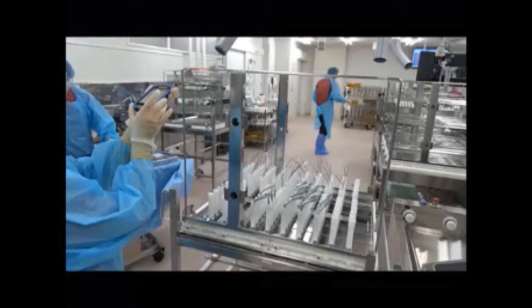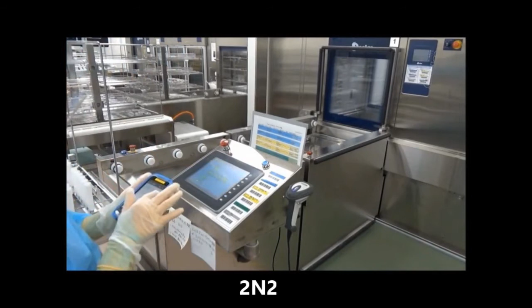The barcodes, which carry washing program IDs, are attached in the washer disinfector. Medical staff read the appropriate barcode with the mobile computer. Then, they read the barcode with the barcode scanner of the washer disinfector. If medical staff scan any incorrect barcodes, the alert starts beeping. When the washing program finishes, the washing cart automatically comes out from the washer disinfector. If there is no problem with the process data such as temperature, it will be displayed on the assembly terminal.